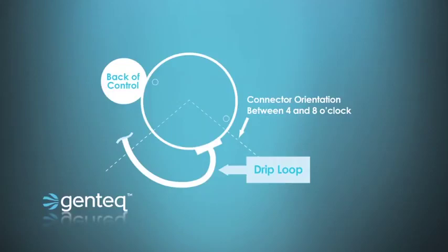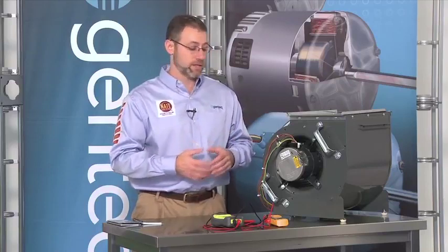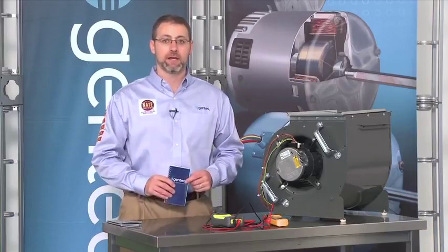So after we've diagnosed the motor and replaced the motor, the last thing that I also like to make sure is that I don't leave a system that could potentially fail another motor. In other words, are there some obvious things I can see that cause this motor to fail, like water damage and airflow problems? If I find either of these situations in the appliance, I want to make sure and solve those problems so that the customer doesn't have a future failure of the motor. Remember that all of this troubleshooting that we just talked about on the X13 motor can be found in the ECM service guide, including an identification chart to help you identify X13 motors from our other ECM motor products.